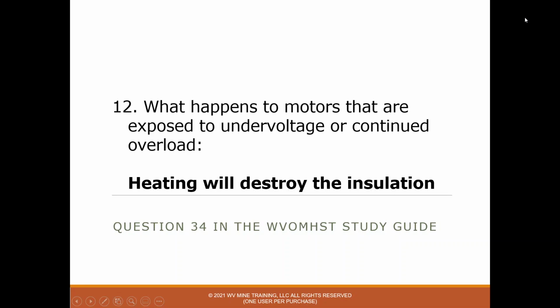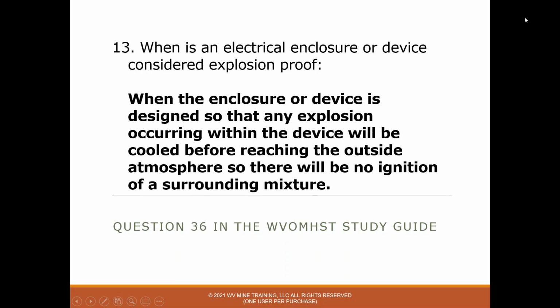12, what happens to motors that are exposed to undervoltage or continued overload? And the answer is heating will destroy the insulation. 13, when is an electrical enclosure or device considered explosion proof? And the answer is when the enclosure or device is designed so that any explosion occurring within the device will be cooled before reaching the outside atmosphere, so there will be no ignition of a surrounding mixture.